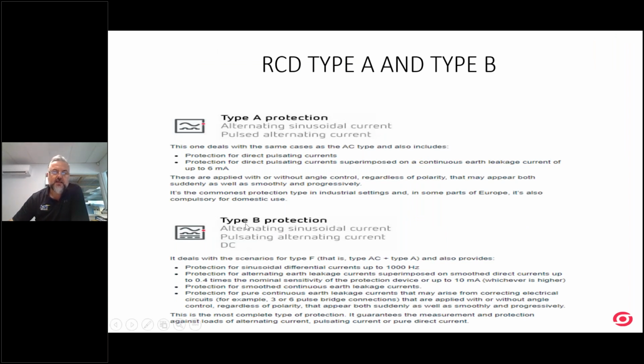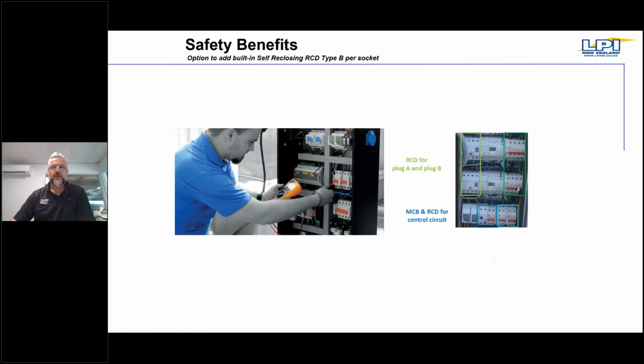One of the main advantages of type B RCD is that, as opposed to the standard RCD, which works only on AC circuits, the type B RCD will be protecting you on both pulsating, alternating, and also DC current as well. So we can supply RCDs, and that RCD can be built inside the actual EV charger, but you still need to have an RCD type B on your point of supply as well.